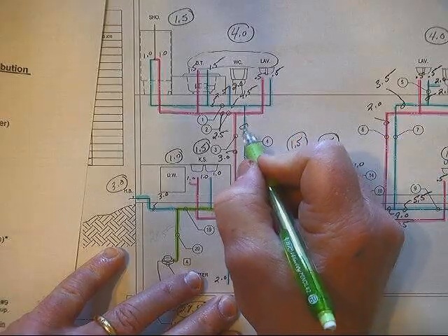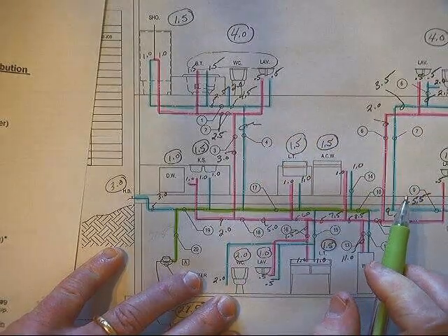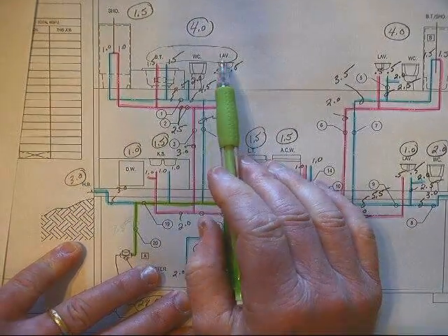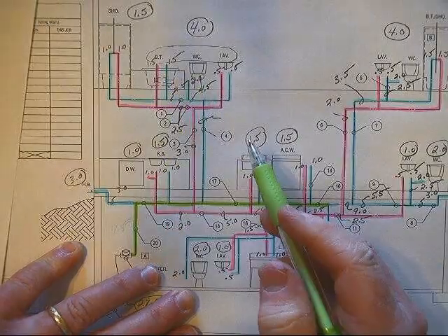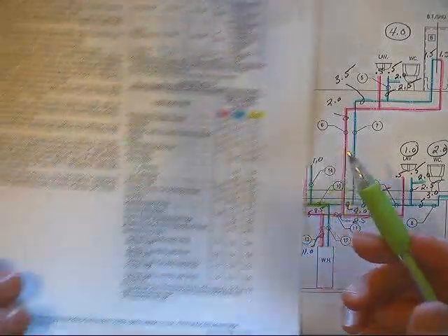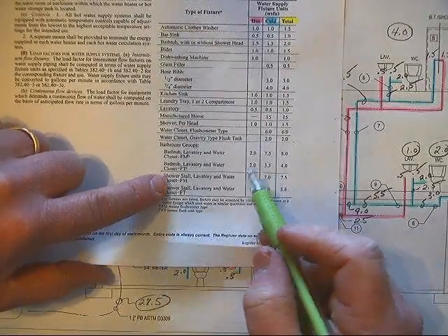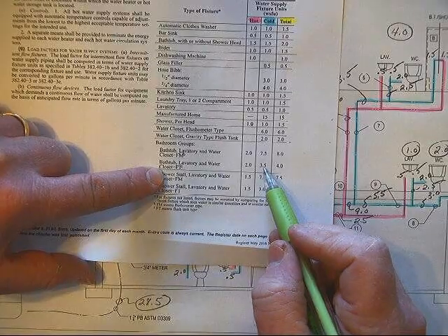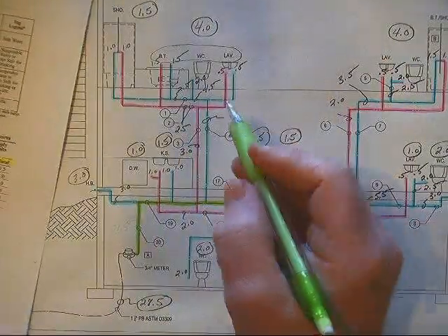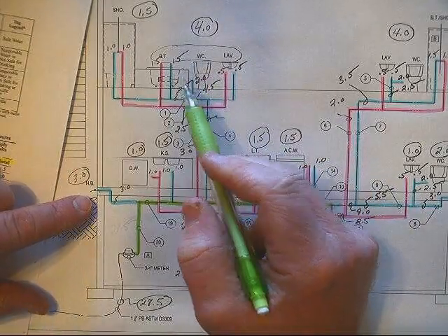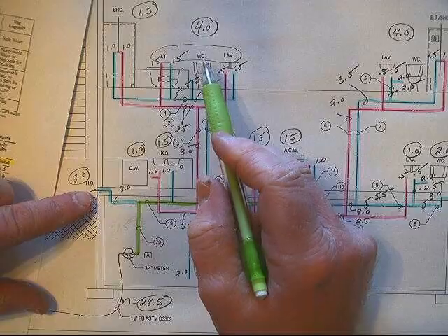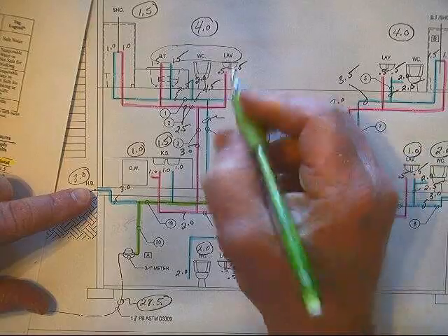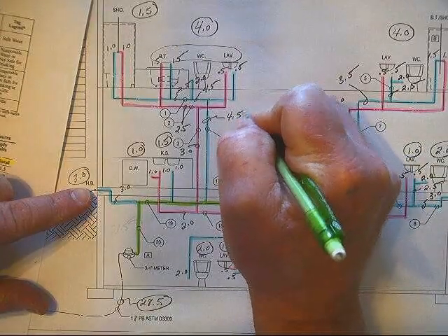As I pointed out before, on the right-hand side, we have a bathroom group. We have a lav, a water closet, and a bathtub. And so for this one, we are going to, again, look at what is the cold load. And for that group of fixtures, the cold load would be 3.5. We will then take the 3.5 of the cold load for the bathroom group, and we will add it to the cold load for the shower, and so that will put us at 4.5.